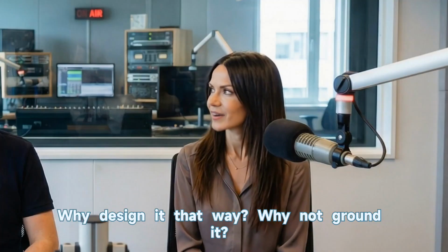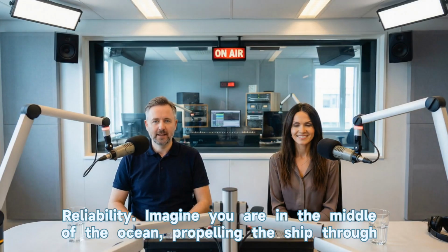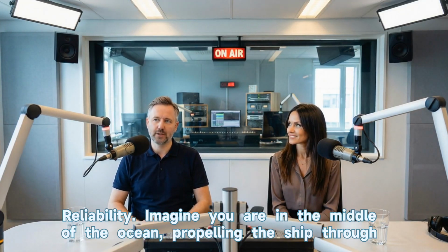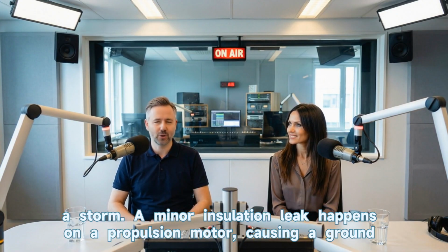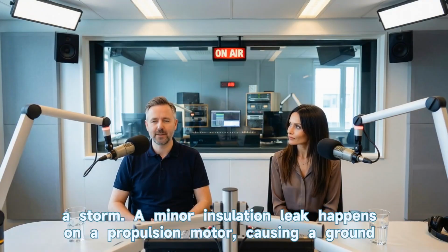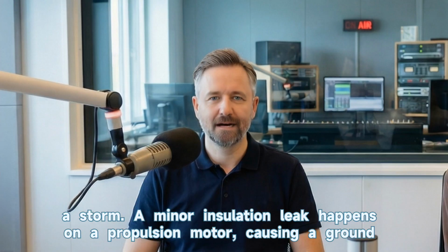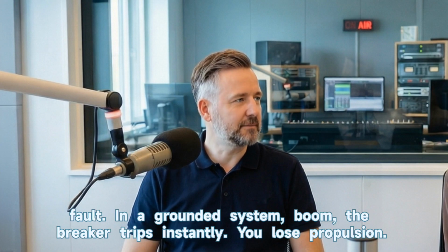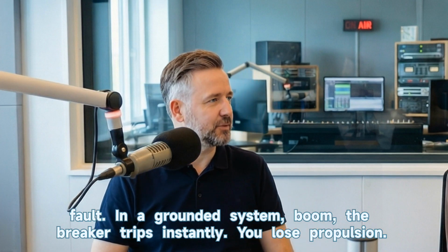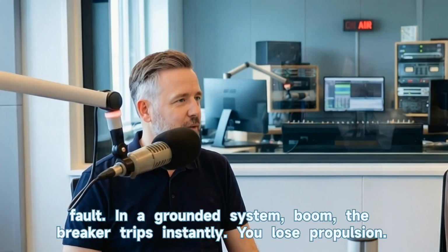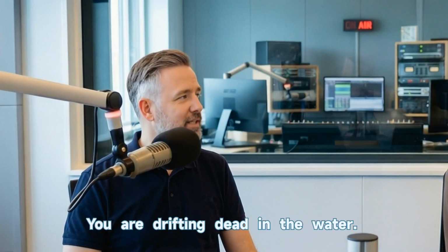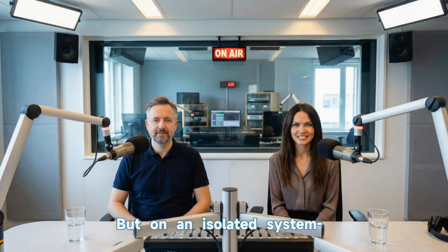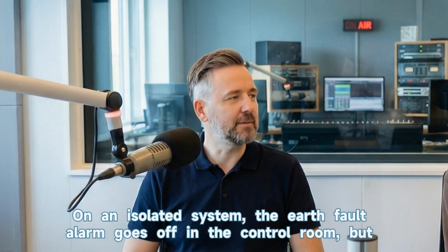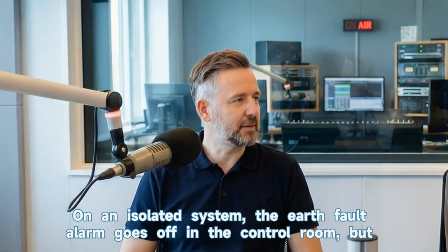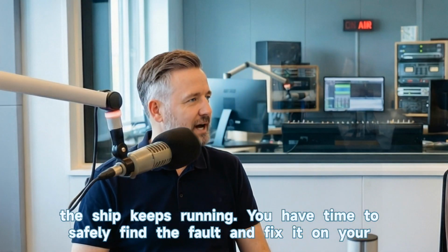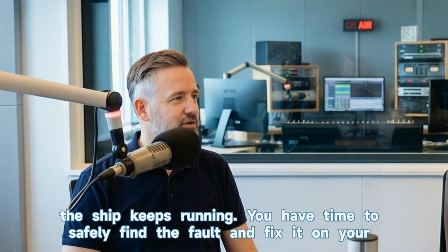Why design it that way? Why not ground it? Reliability. Imagine you are in the middle of the ocean, propelling the ship through a storm. A minor insulation leak happens on a propulsion motor, causing a ground fault. In a grounded system, boom, the breaker trips instantly. You lose propulsion. You are drifting dead in the water. But on an isolated system... On an isolated system, the earth fault alarm goes off in the control room, but the ship keeps running. You have time to safely find the fault and fix it on your own terms.